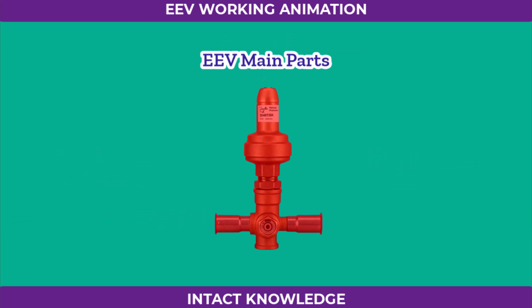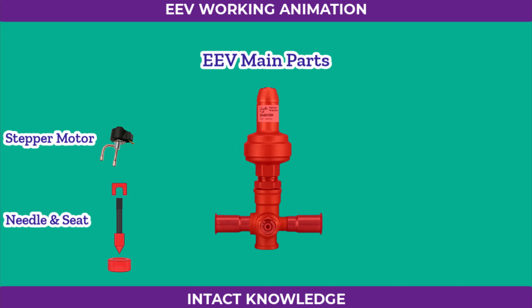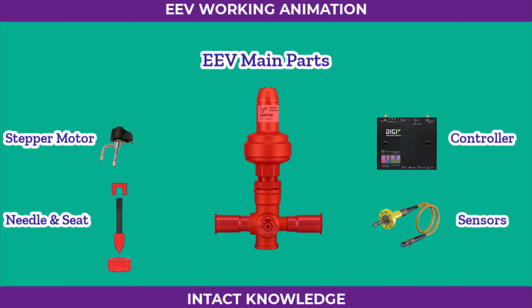Let's now understand the main parts of an EEV. Stepper motor. This is the core element of the valve. It moves in precise increments to regulate the refrigerant flow accurately. Valve needle and seat. These two parts manage the valve's opening and closing, controlling how refrigerant passes through. Controller acts as the system's brain, sending control signals to the stepper motor. Sensors. These detect temperature and pressure at the evaporator's inlet and outlet.